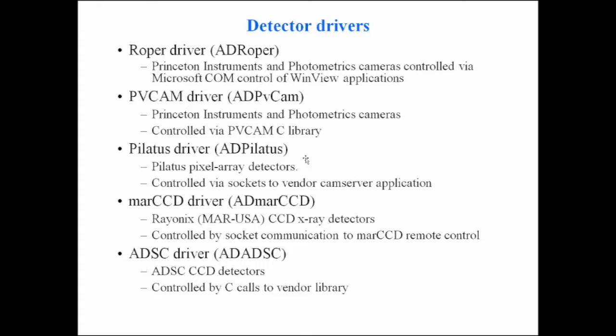There's a driver for the Pilatus pixel array detectors, an example of using sockets to the vendor's CamServer application. It's not a great architecture because Dectris provides no way for an area detector driver to directly get data from the detector — the detector has to write a disk file (a TIFF), and then area detector reads back the TIFF to get data into the NDArray so you can run it through plugins. It's not ideal, but that's what we have.